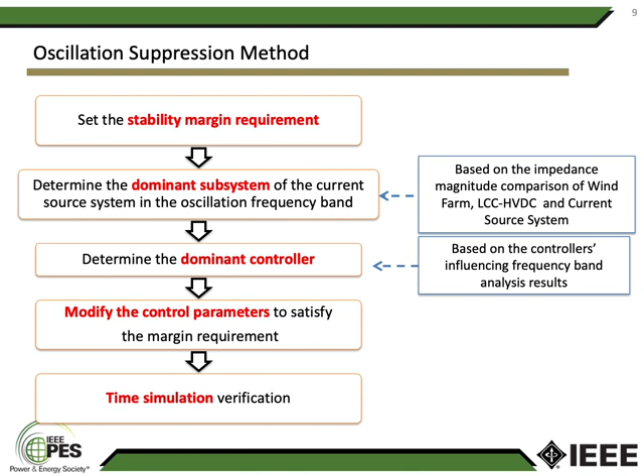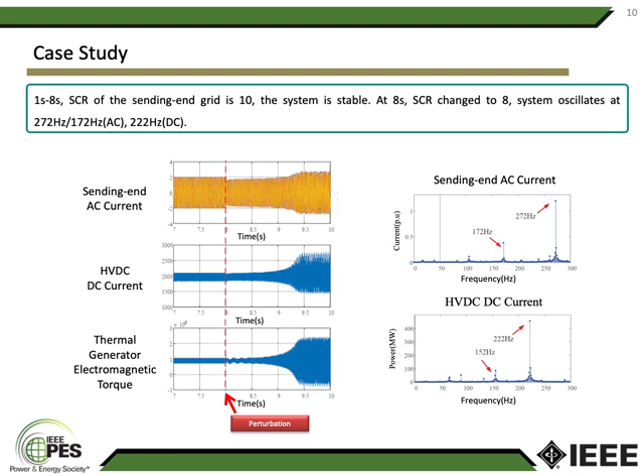In order to verify our analysis and suppression method, one case is studied within 1 second to 8 seconds, where the short circuit ratio of the sending end is 10. The system is stable, as shown in the left figure. At 8 seconds, as the ratio changes to 8, the system oscillates at 272 Hz and 172 Hz at the AC side, and 222 Hz at the DC side, as shown in the FFT result in the right figure.